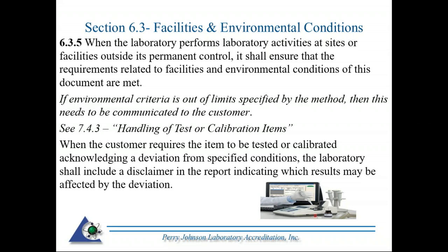7.4.3 in handling of testing calibrations items. So if you were at a customer's location doing testing and or calibration, and they were outside your protocol, as stated here from 7.4.3, when the customer requires the item to be tested or calibrated, acknowledging a deviation from specified conditions, the laboratory shall include a disclaimer in the report indicating which results may be affected by the deviation.